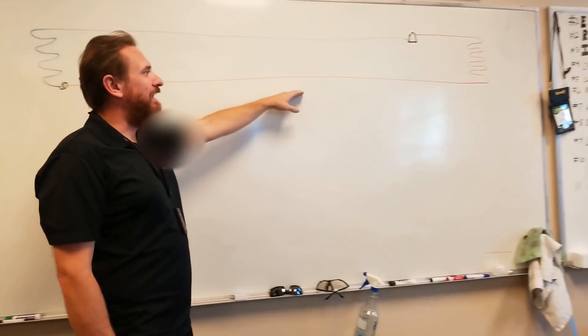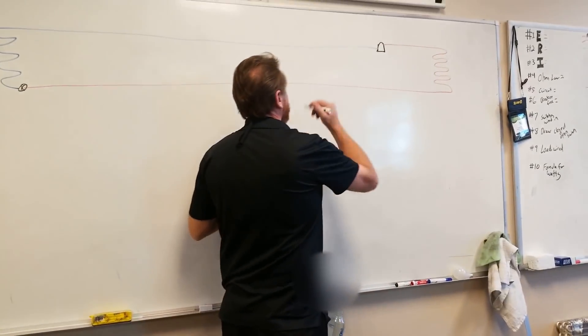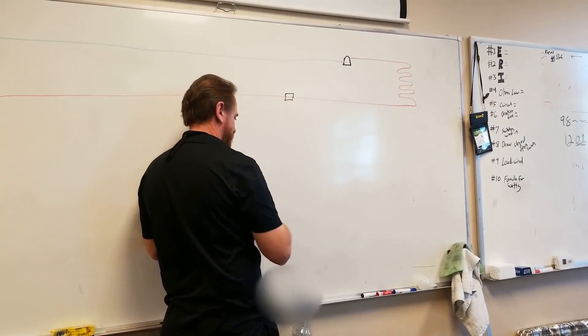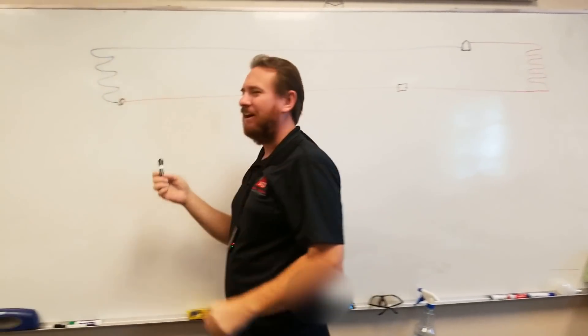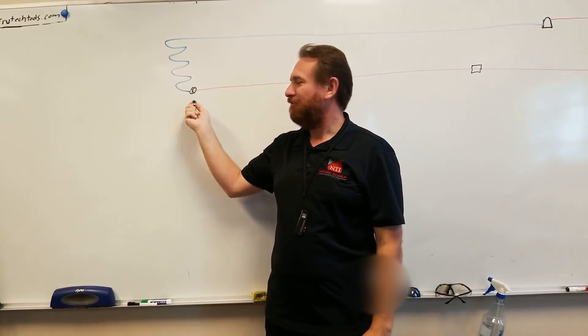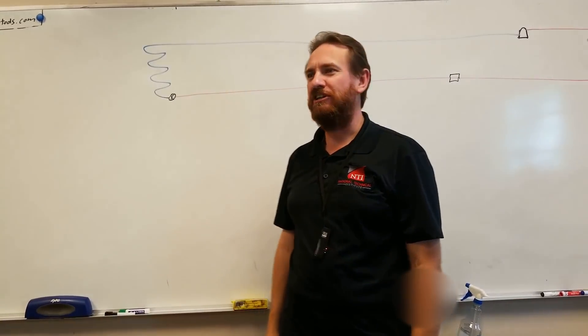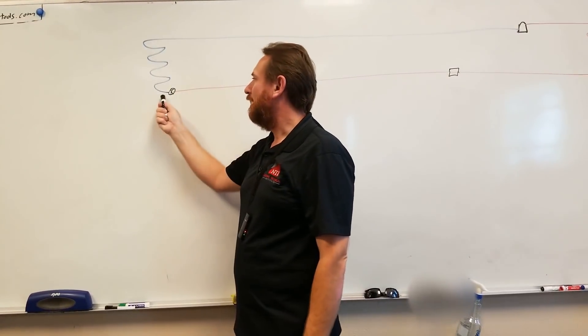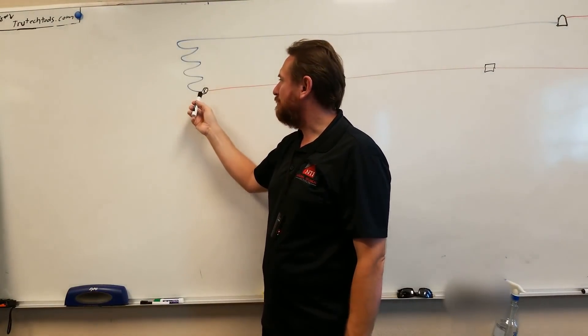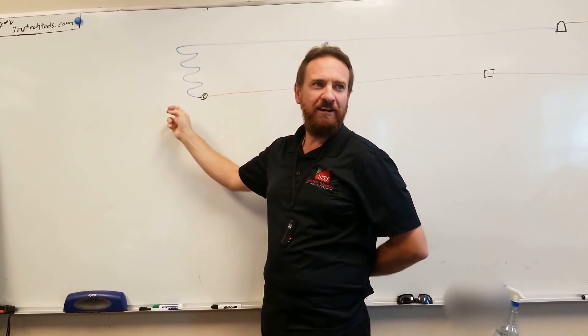We have our liquid line, and somewhere in there we have to have our liquid line filter dryer. The metering device is a different component. Then we get to our metering device, which restricts the refrigerant from a high pressure liquid to a low pressure saturated mixture — approximately 75% liquid and 25% vapor. That drops the saturation temperature below the temperature of the air.